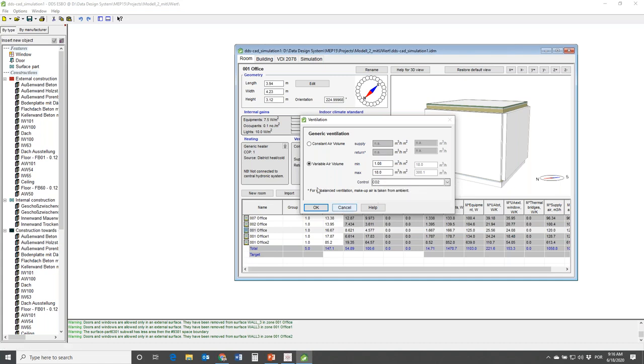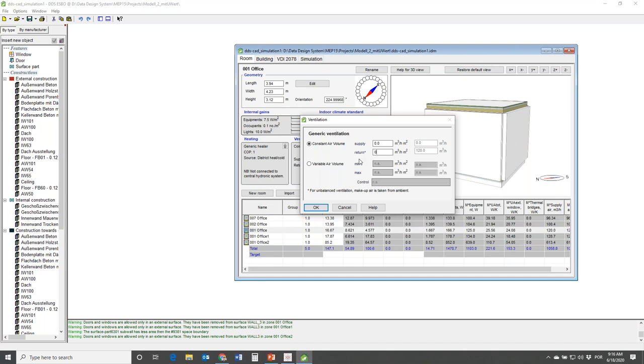For Room 001, we say we have no ventilation, because this is the case where you may want to design for a fan coil system with no mechanical ventilation from the air handling unit. So we just specify it as a constant air volume system with no ventilation rates.